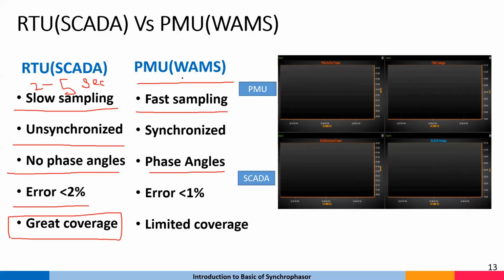With the PMU system, it provides data at let's say 25 hertz, so in each 1 second I get 25 samples, meaning one sample every 40 milliseconds. That's quite high compared to one sample every 2 to 5 seconds. It is also time synchronized, which makes it wonderful for operational purposes. If it weren't time synchronized, we wouldn't get a complete picture of the system at a particular instant. It's like having a camera that clicks a picture of the complete power system from all points, giving a complete overview of magnitude and phase angle at each point at that instant.